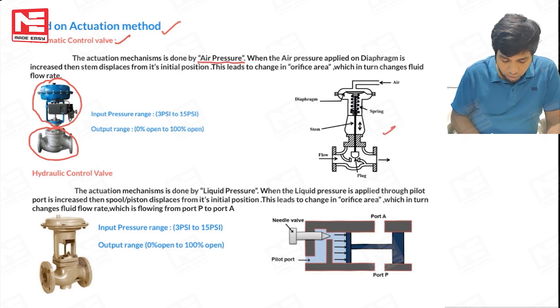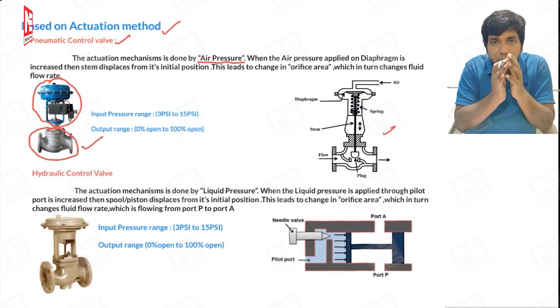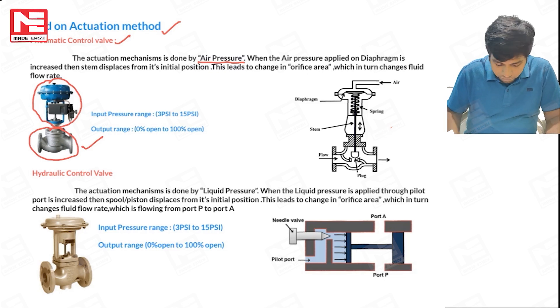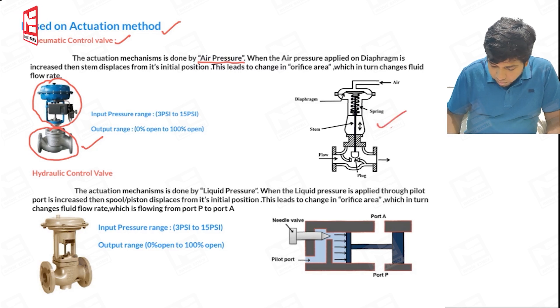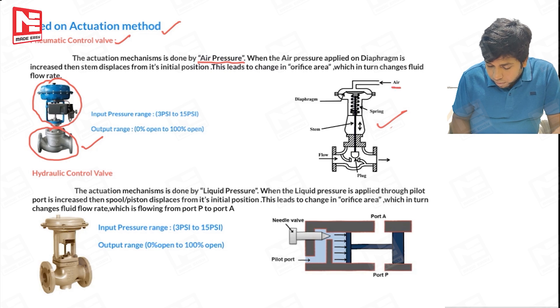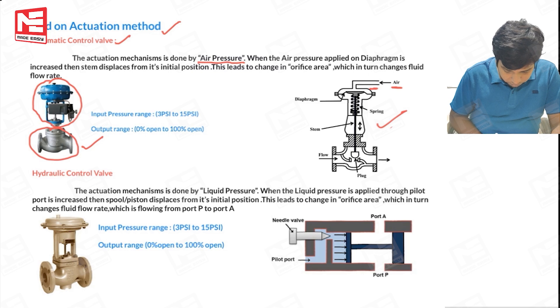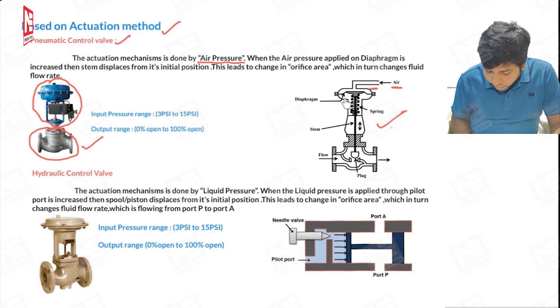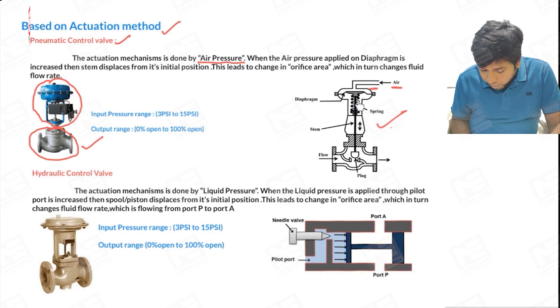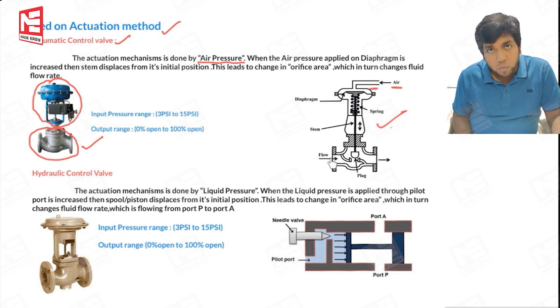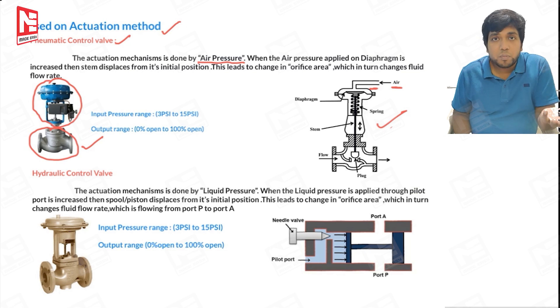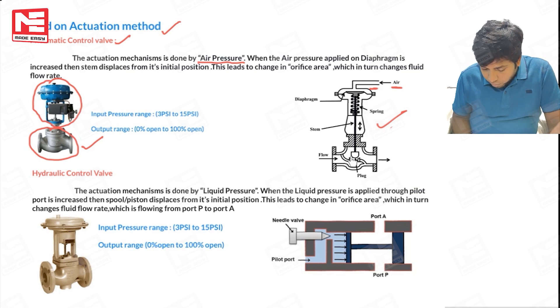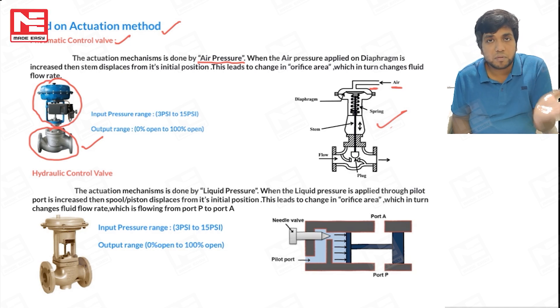When you buy a control valve in a shop it looks like a unit, but if you open it the internal structure reveals the components. Air is supplied through a port to the diaphragm. The diaphragm is elastic material, and it is attached to a stem at its lower end. We also have a spring above the stem. This supporting mechanism is called the bonnet. The fluid enters at the inlet and exits at the outlet port.